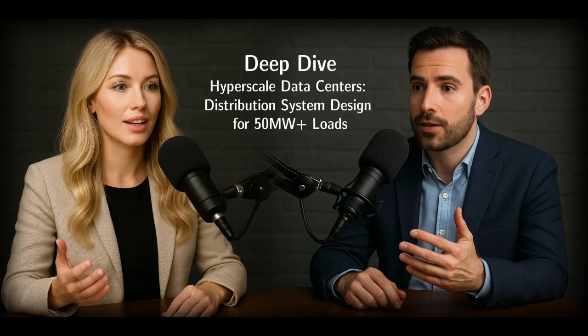Notice that's similar to the 35 megawatt load at 25 kilovolt. Right, higher voltage, lower current for the same power. Exactly. A single 795 kcmil aluminum conductor could handle that. And the voltage drop, almost negligible, maybe 0.8% over 20 miles. But you definitely need full transmission-grade protection, usually involving high-speed communication like fiber optics.